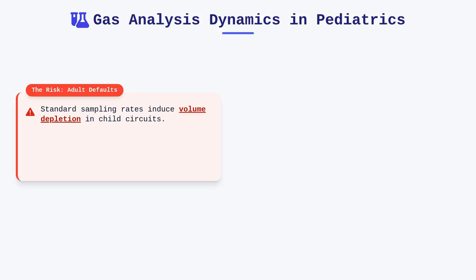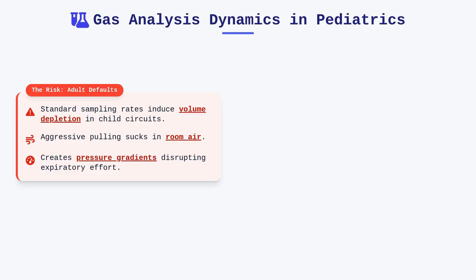Beyond the physical hardware, we must account for the dynamics of gas analysis within the internal circuitry. Standard gas analyzers are often configured to sample gas at a rate that is perfectly appropriate for adult tidal volumes, but these rates can actually induce volume depletion in a child's circuit. If the analyzer pulls too aggressively from the patient's side, it can suck room air into the circuit or create a pressure gradient that interferes with the patient's expiratory effort.